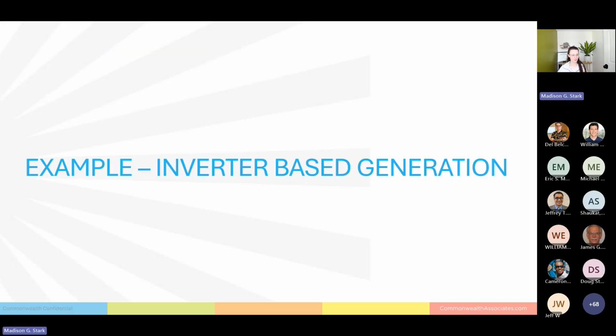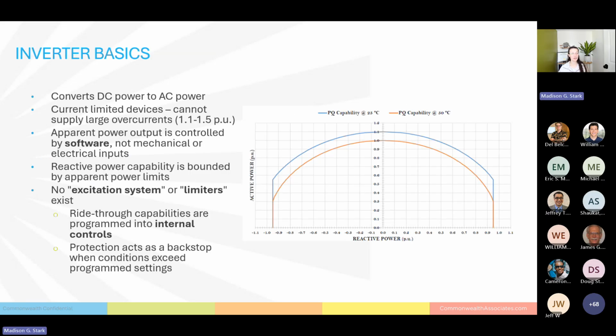All right, moving into inverter-based generation. Quick touch on what is an inverter, what does it do? At its core, an inverter converts DC power to AC power. So where does that come into play? With a lot of your DC-based generation. So you see it with PV arrays, which are DC. You can see it with battery plants, which are not technically generation, but batteries operate in DC, so they all have inverters to connect them to the grid. You see it in some types of wind turbines. Type 3 and type 4 wind turbines involve inverters, although they actually have converters, but they have an inverter connecting them to the grid.